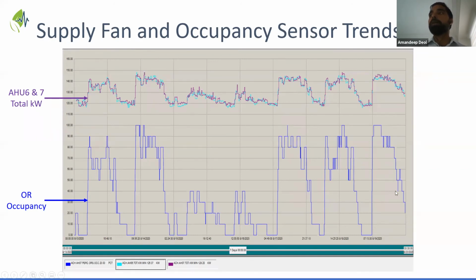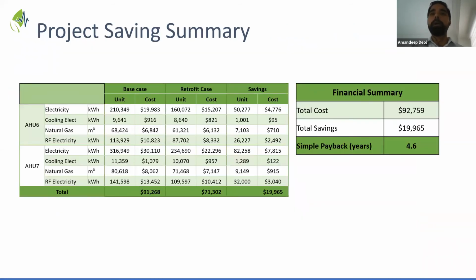The blue graph at the bottom of this chart is the actual occupancy sensors converted into percentage occupancy. So you can see at nighttime when none of these rooms is occupied, the fans go down to around 120 kilowatts of total demand. This triggered one thought with us: we were expecting higher savings on this project, and this brought us to review what's going on in this project.